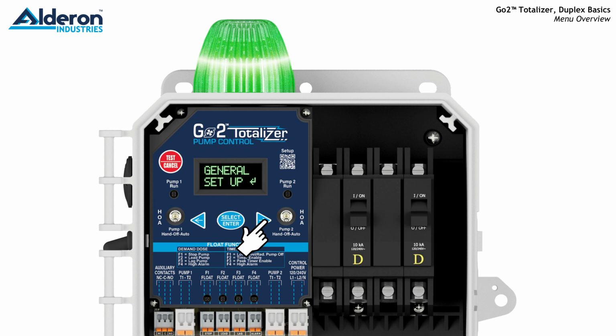If you want to make changes to the general setup, you can change alarm reset type, silence time reactivation, green beacon changes, and password code. Select Alarm Reset if you want to change from factory default of automatic reset to manual reset of alarm. If manual alarm reset is enabled, then when an alarm is activated, the buzzer will remain on even if the alarm is cleared. This will require the alarm to be reset by an operator pressing the required button to acknowledge that alarm occurred.